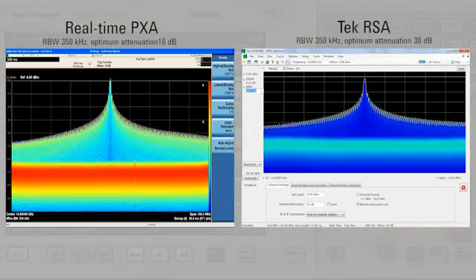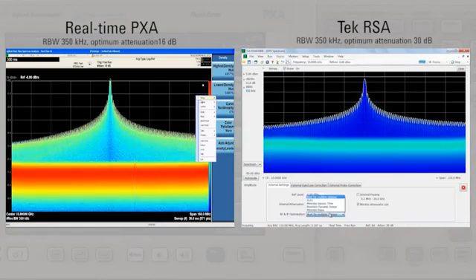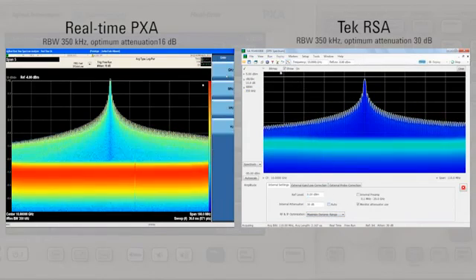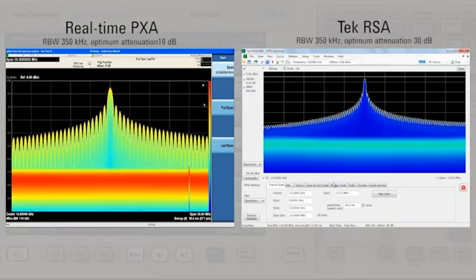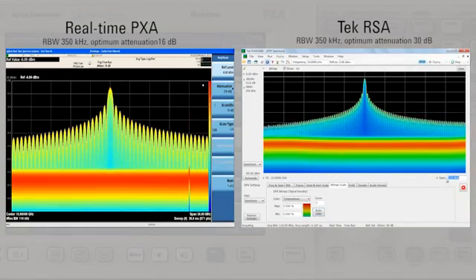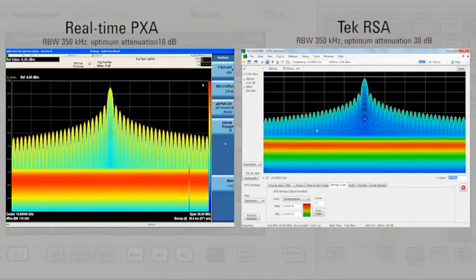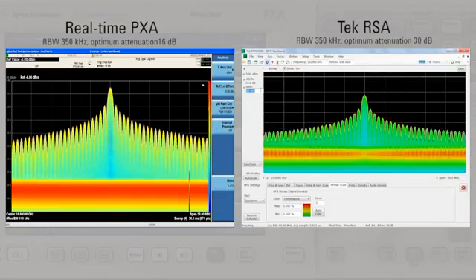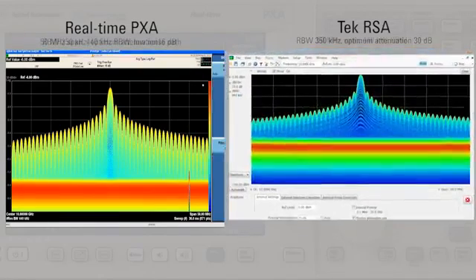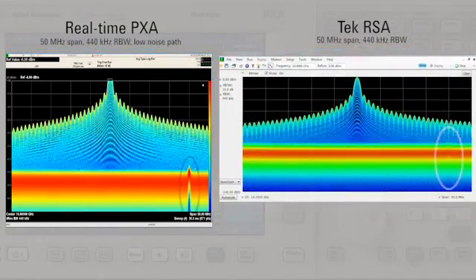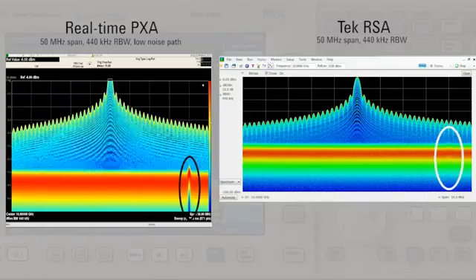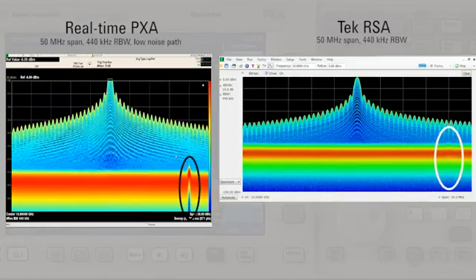I'm going to optimize each instrument to make this challenging dynamic range measurement. The PXA can measure the signal accurately with 16 dB of attenuation. Fortunately the PXA has 2 dB step attenuation in RTSA mode to help find the dynamic range sweet spot. A preamp will not work well here because of the larger input signal.